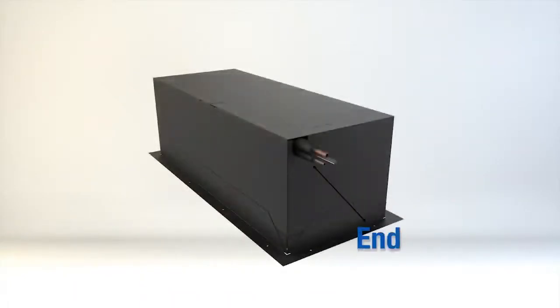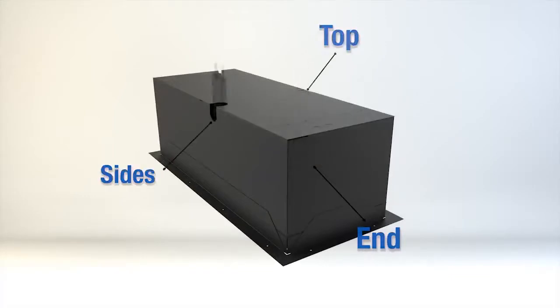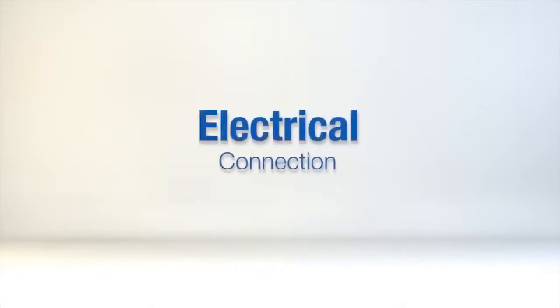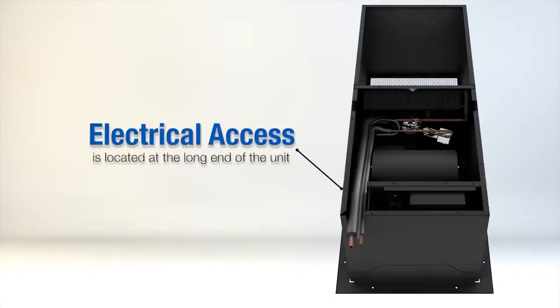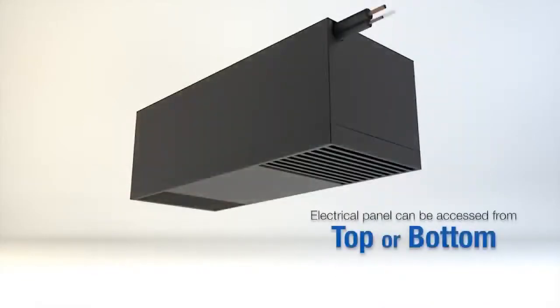The unit comes with the line set stubbed out of the short side from the factory, which eliminates the need for brazing inside the unit. There is also additional access from the top and each of the long sides. The electrical access for the evaporator is located on the long end of the unit. The electrical panel can be accessed from the top or bottom of the unit.